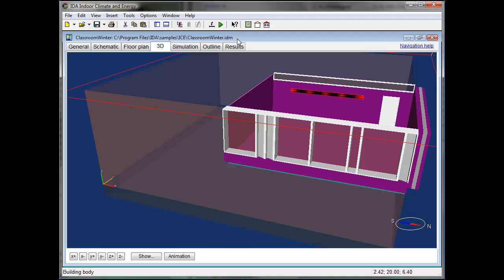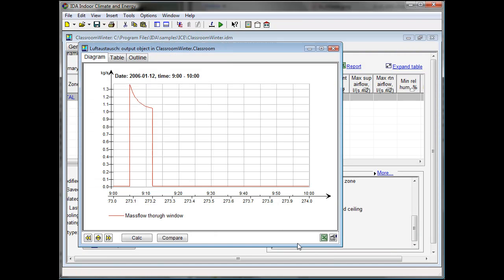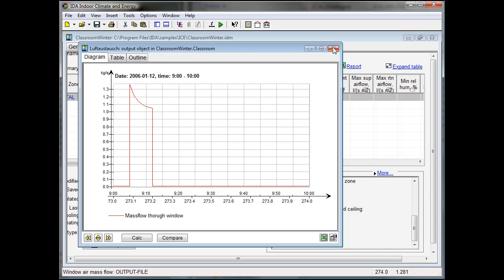As simulations are already done, we can directly have a look at the results. First of all, the mass flow through windows. We can see here a time slice of 1 hour with a 10-minute break and the windows being opened the first 7 minutes of the break. We can see a mass flow of 1 kg or cubic meter per second through the opening.